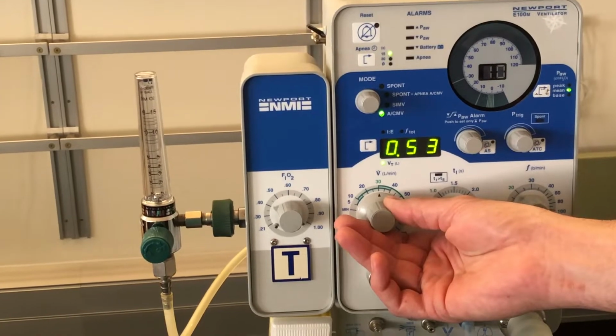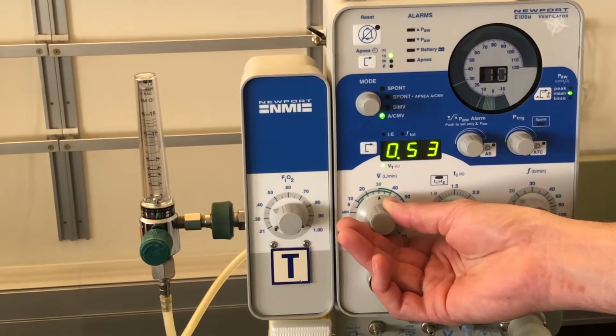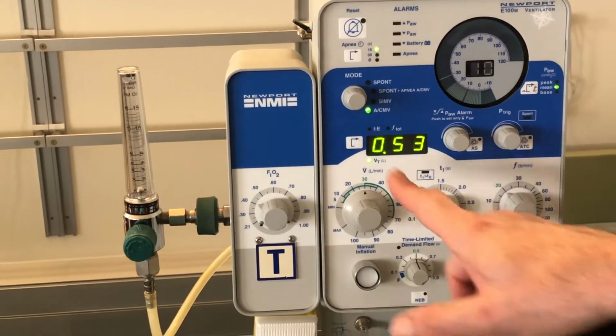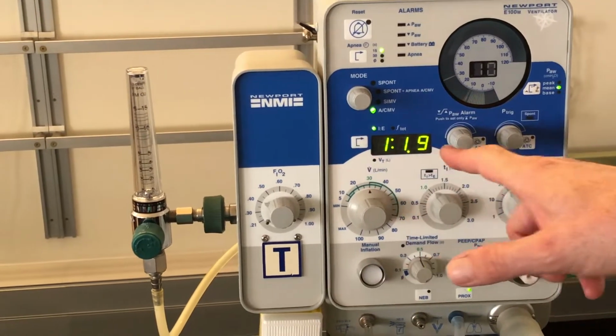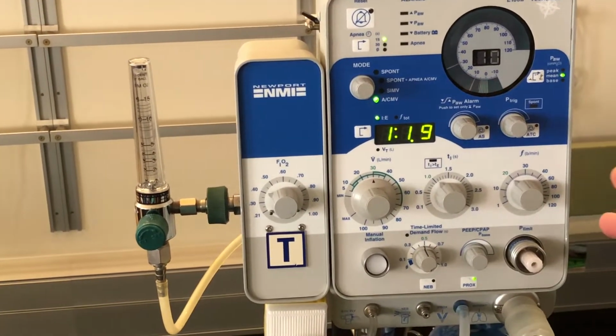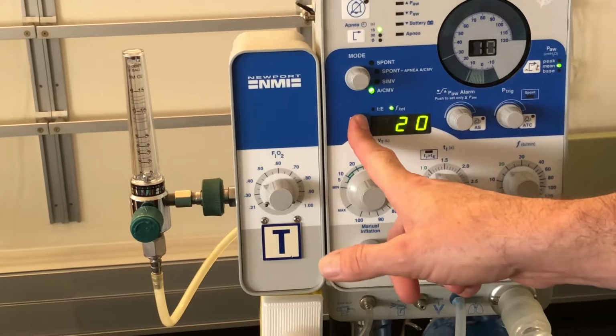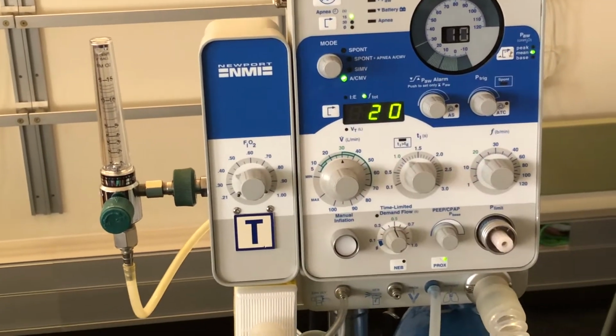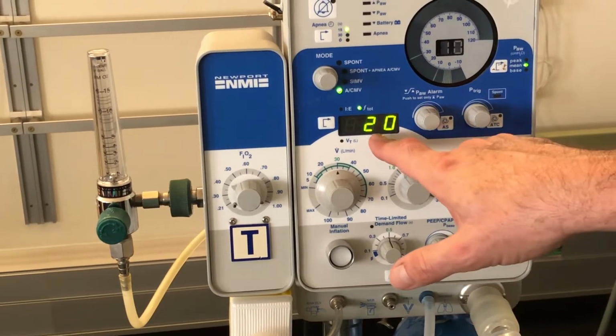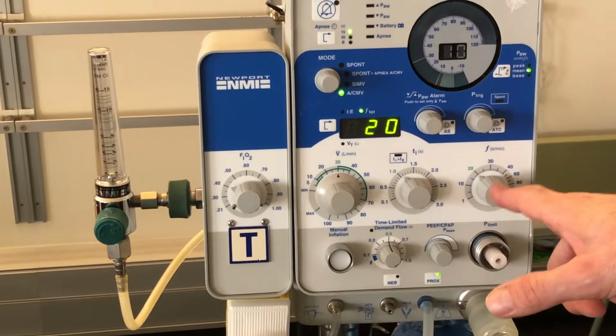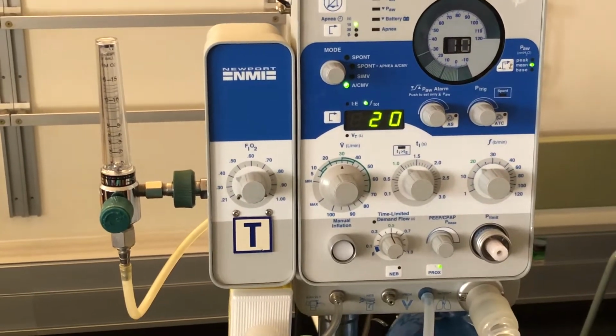So I'm just going to tweak it, but you'll see the tidal volume is very, very close to 500 mils. The IE ratio is almost exactly 1 to 2, which is what we set. And the total breath rate at the moment is 20. Remember, the total breath rate is 20 because we've set 20 and there's no patient breathing on the circuit.